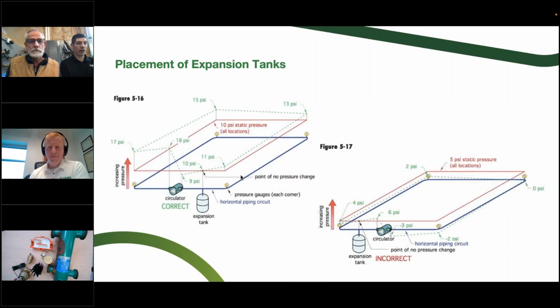Okay, so let's talk about that vent at the top, where you wanted to have the little check valve to prevent air from coming back into the system. So here's where that could happen. Best case scenario, we're always pumping away from the expansion tank. So we've got the expansion tank right here. Our circulator is after that. And in the green dotted line, you can see what that does to the pressure throughout this loop.